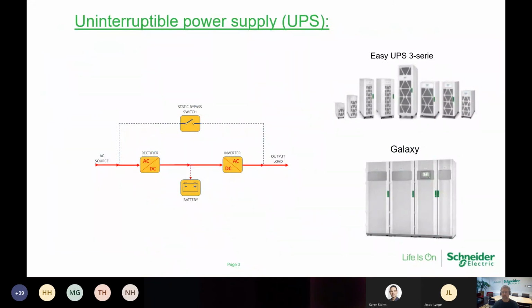We design UPSs, and a UPS is designed to provide reliable, clean power to a load, for example an IT system in a data center, even in the event of a power failure or disruption in the main power source. Most UPS systems do this by performing a double power conversion: they take AC power from the main source, rectify it to DC to perform filtering and also charge the UPS batteries, and then convert the power back to AC for the load. On the right side, you can see some different types of UPSs.